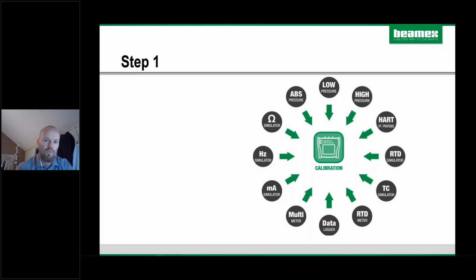When it comes to calibrators, you also have to recalibrate them, recommended every year. You can also have calibrators communicating with and controlling pressure controllers. So instead of manually pumping pressures using hand pumps, you can have a pressure controller and a calibrator communicating with each other, giving you a fully automated calibration.